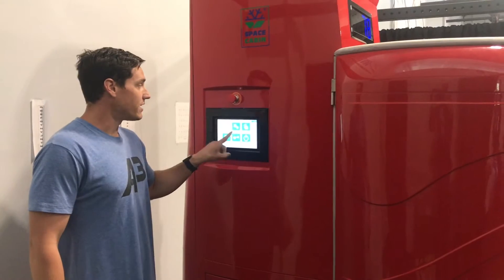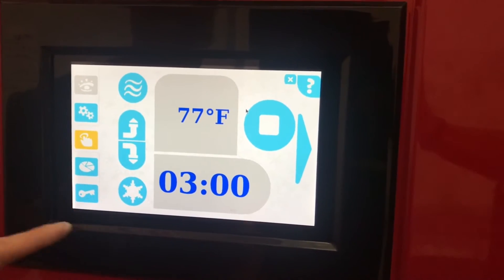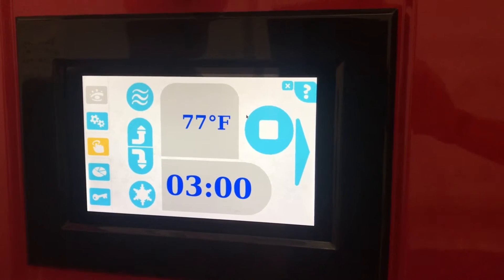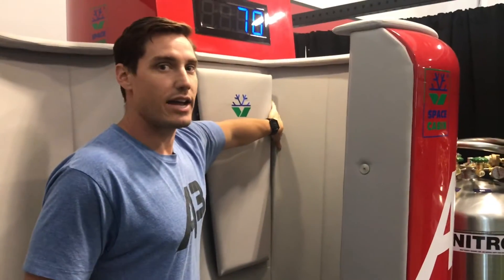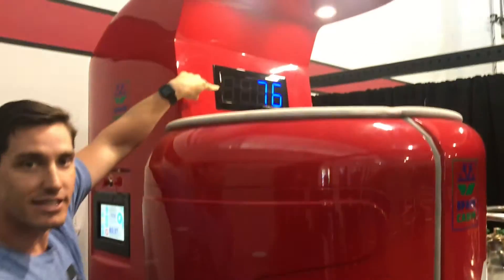The first thing you're going to do is touch this icon — it's the hand. You've got a snowflake and the airwaves at the top. The snowflake is how you're going to chill the unit. Right now, as you can see, it's 77 degrees Fahrenheit — it needs to be significantly colder than that. You have a default timer of three minutes. Press the snowflake and it's going to charge or prime the unit and start to chill it. When you open the door, there's going to be a rush of cool air and nitrogen is going to start to flow through the unit. Keep that door closed and you'll notice on the temperature icon that the temperature will start to drop.